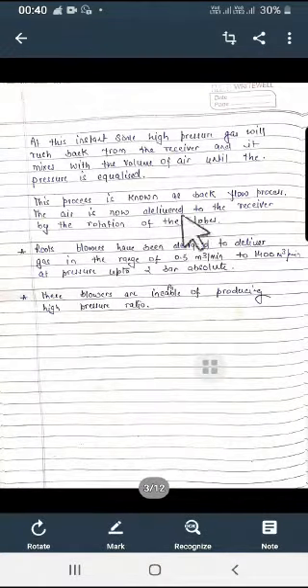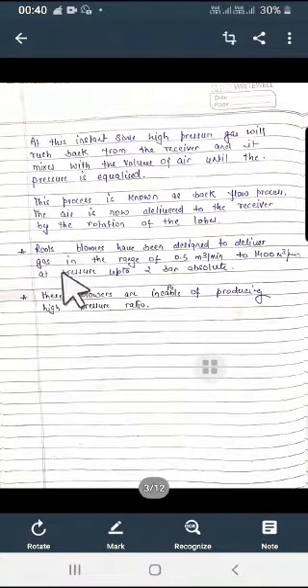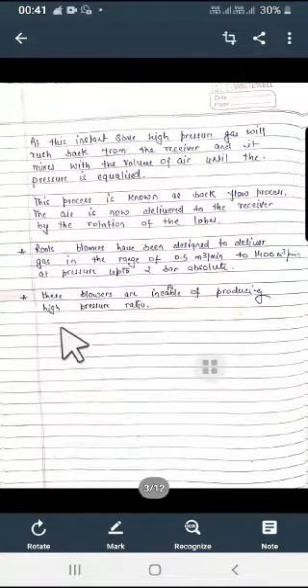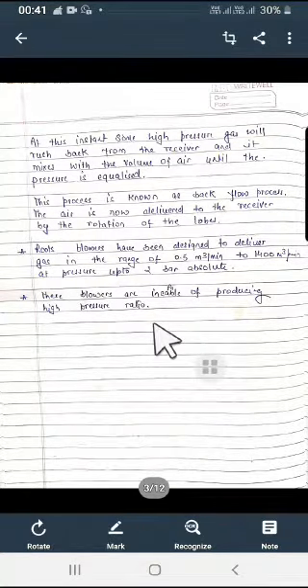Roots blower compressor have been designed to deliver gas in the range of 0.5 meter cube per minute to 1400 meter cube per minute at pressure up to 2 bar. These blowers are incapable of producing high pressure ratio.